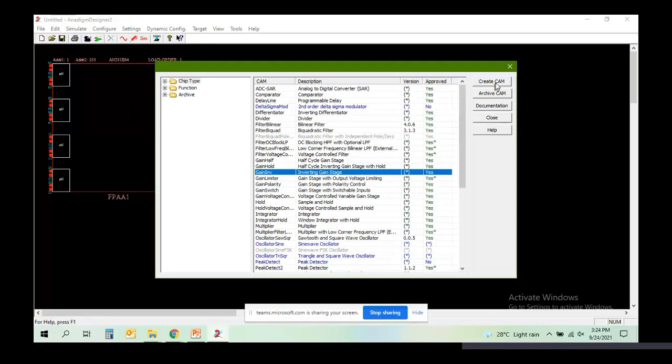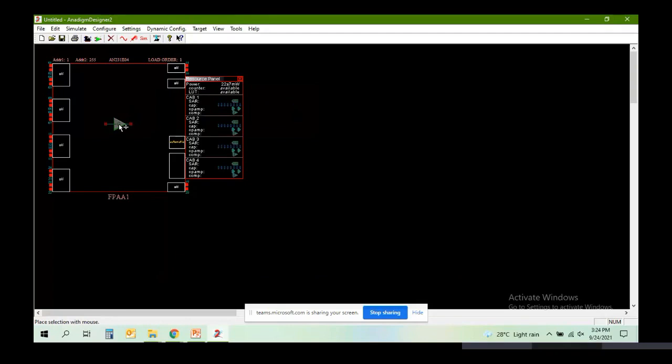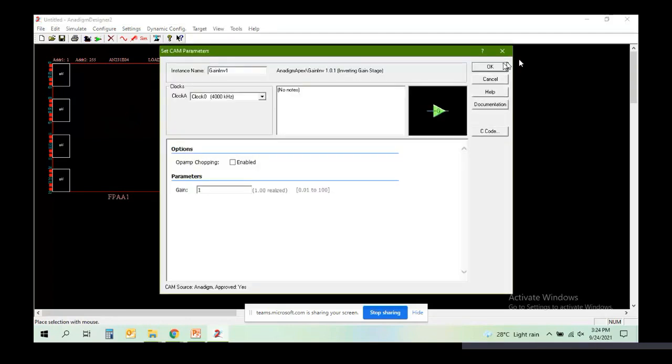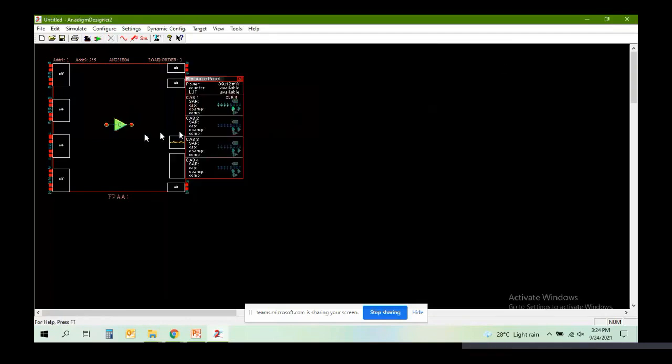That's what I'm asking. It is automatically on CAB 1, right? It will take up the resources automatically. We don't have a control over that. So if I place one more function, it is taking the same CAB resources. If I place one more, it is taking another CAB's resources, because CAB 1 doesn't have any capacitor left to use.